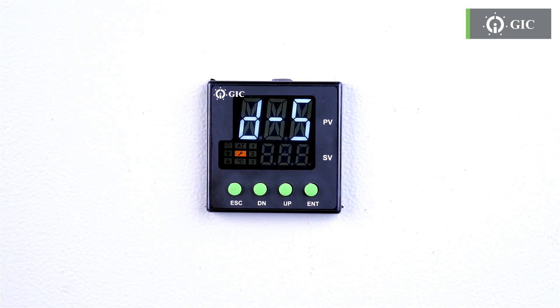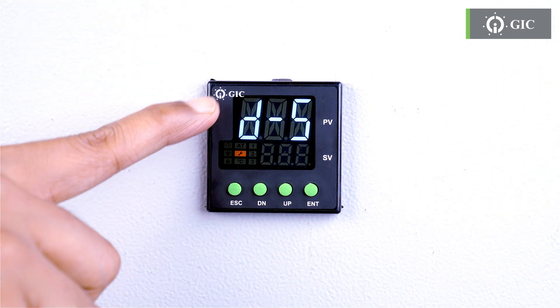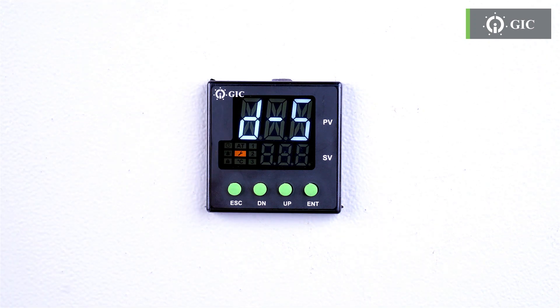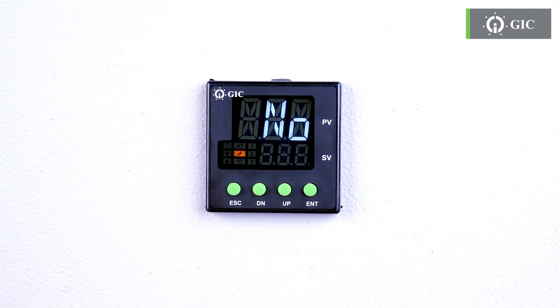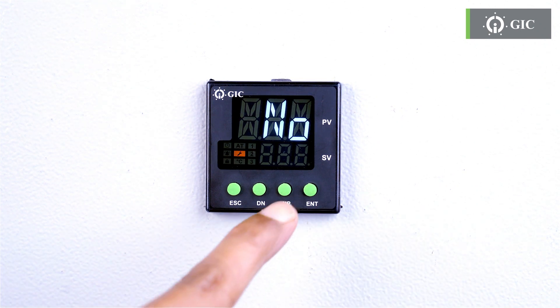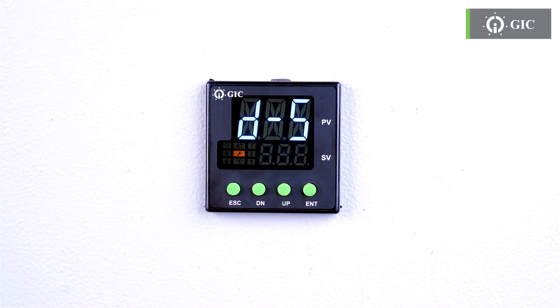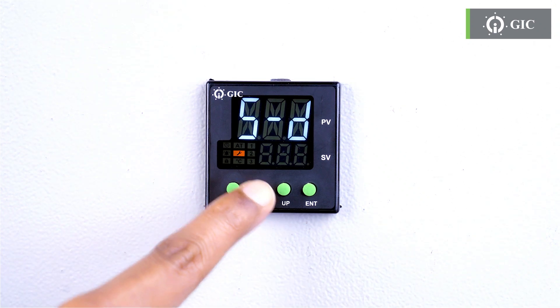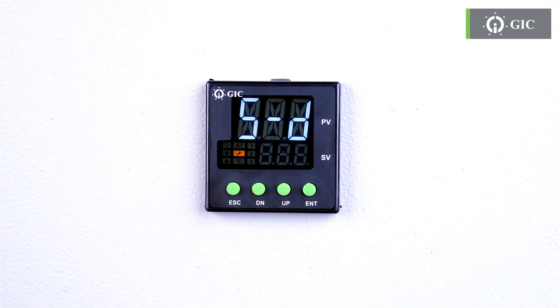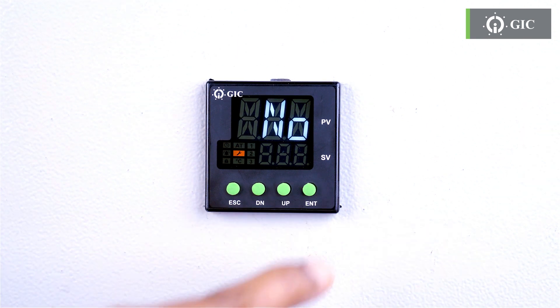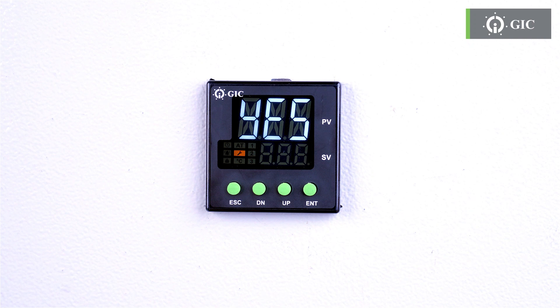To begin, insert the memory card, and on the display you will see D/S, which means display to card. This will copy the program from the device to the inserted memory card. Press enter. The device will show NO — press the up key and the device will show YES. Press enter. If the screen displays D and E, it means the program has been copied successfully. In the same way, you can also copy the program from the SD card to your device using the S/D function, that is SD card to display.